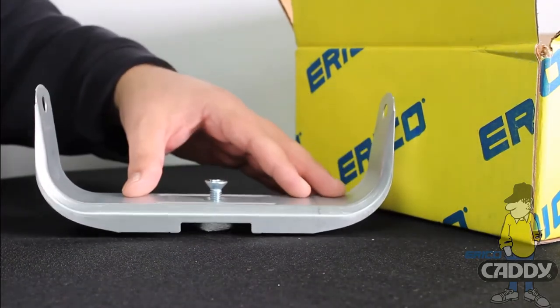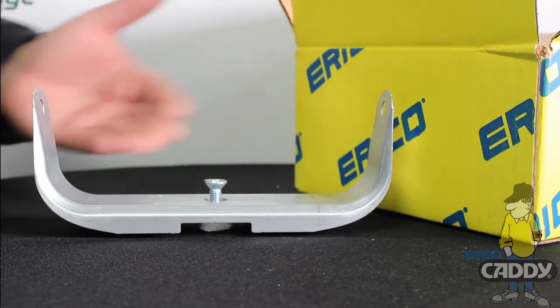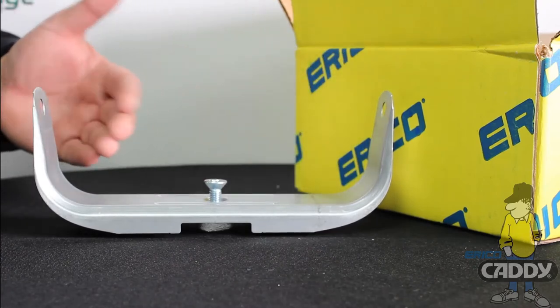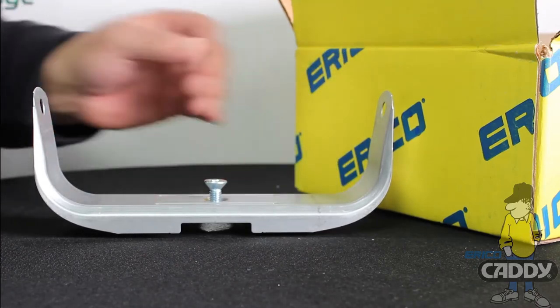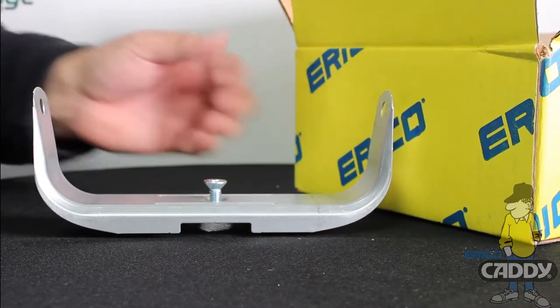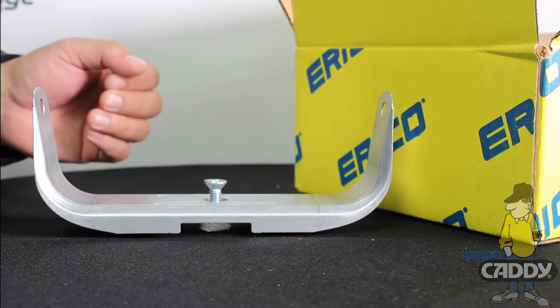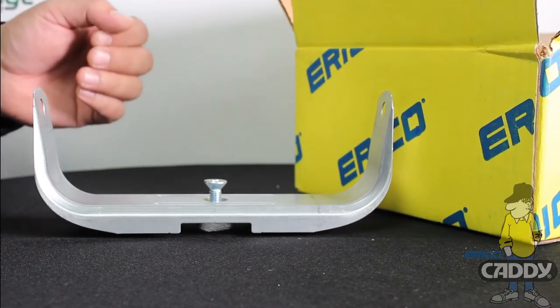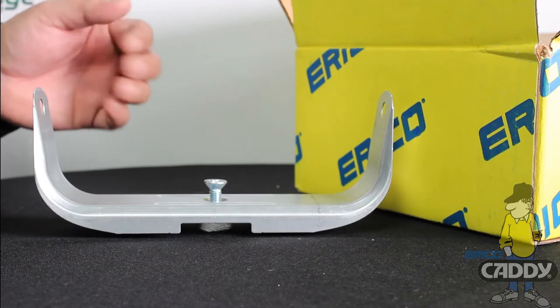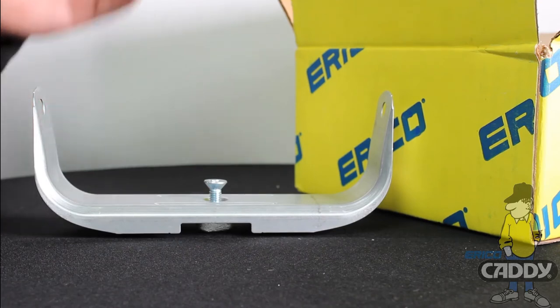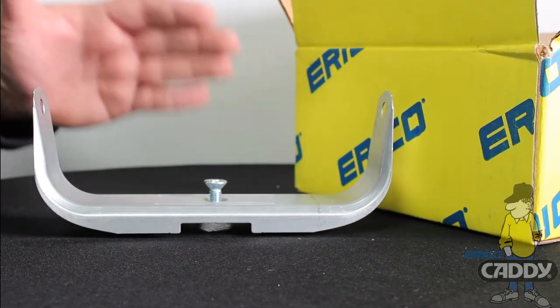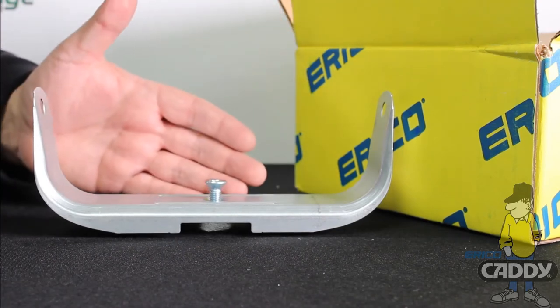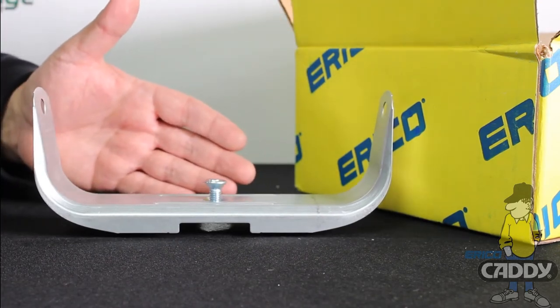You're probably wondering what the spacing is here - it's eight inches. There is a model that's bigger than this; this is the 200, that one's the 300. The 200 on strut will support 320 CAT5E cables or 200 CAT6 cables.